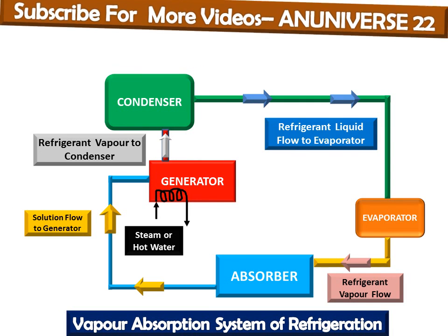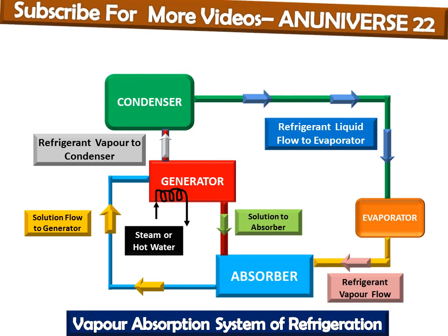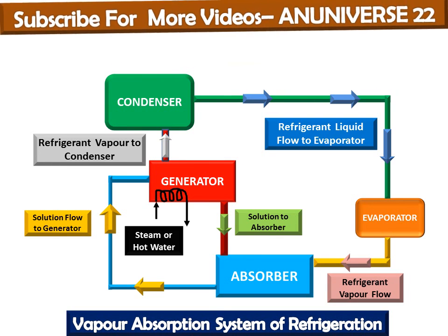The liquid refrigerant then passes on to the evaporator, completing the refrigerant cycle. The absorbent flows back from the generator to the absorber. Heat is generated when the refrigerant is absorbed by the absorbent, which is known as the heat of absorption or heat of dilution.